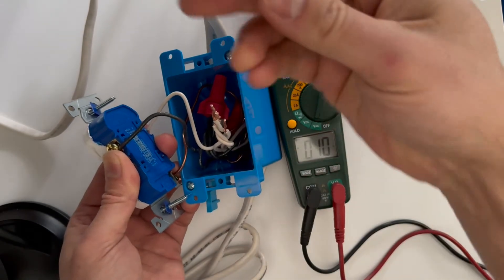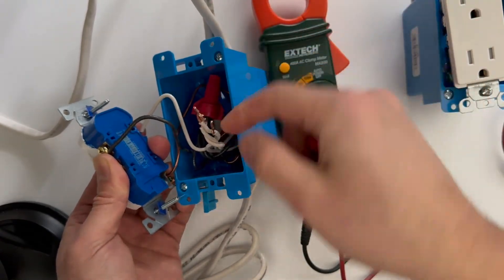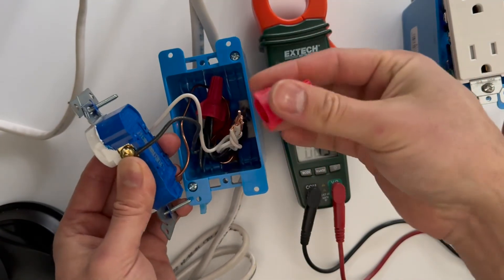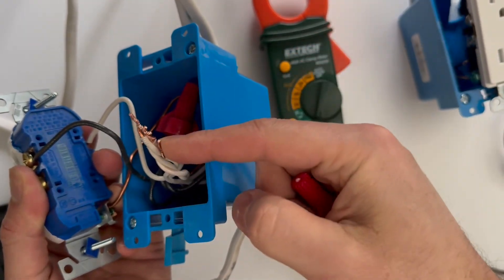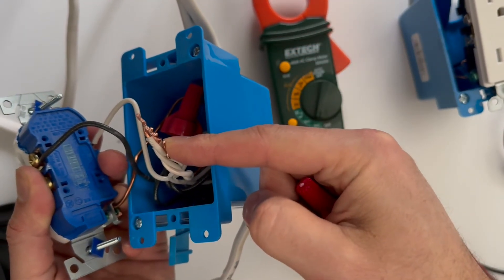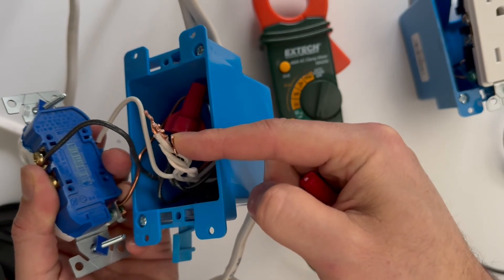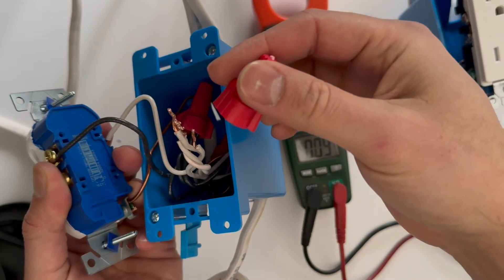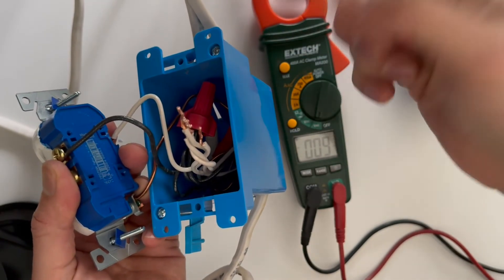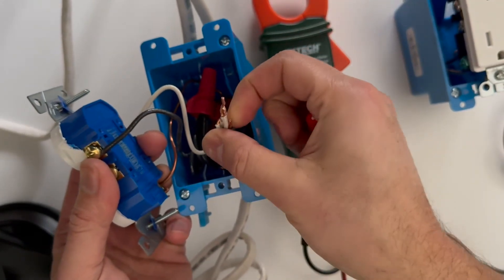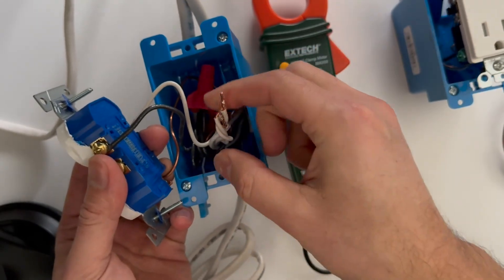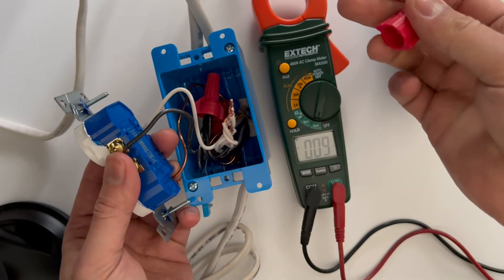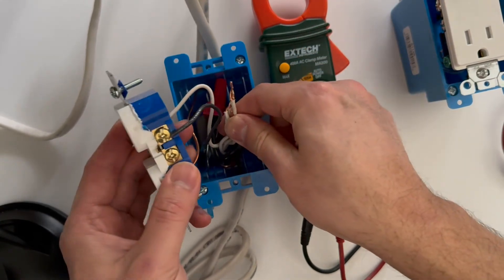You have to inspect this manually. You'll be taking a look and you'll realize that when this connection was made with this wire nut, one wire was barely making a connection and it was working for quite some time, but then it just got disconnected. This is the most common one that happens.